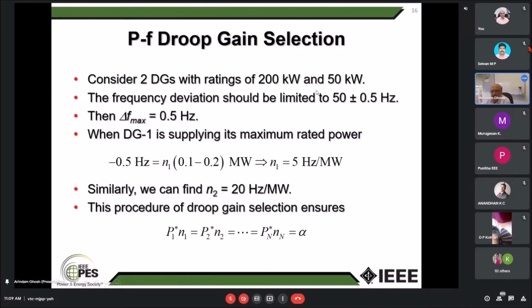Now, suppose I say I maintain the frequency deviation to plus minus 0.5 hertz. That means I don't want to let the frequency go above 50.5 hertz and fall below 49.5 hertz. That 0.5 hertz is just a number. It can be 1 hertz too. It doesn't make any difference. It depends on the kind of load that you have. If your load, like adjustable speed drives or something, is not able to tolerate much frequency deviation, then it is better to restrict the frequency variation within a specified limit.